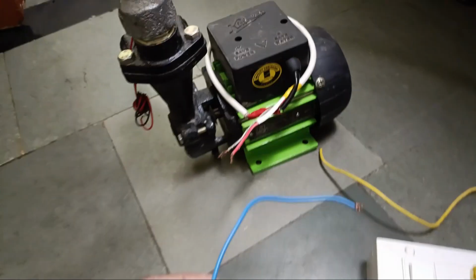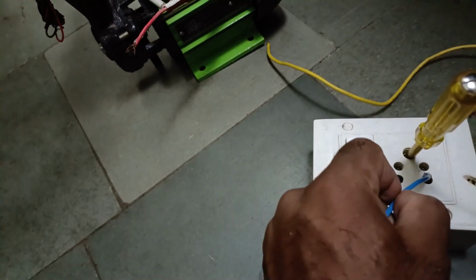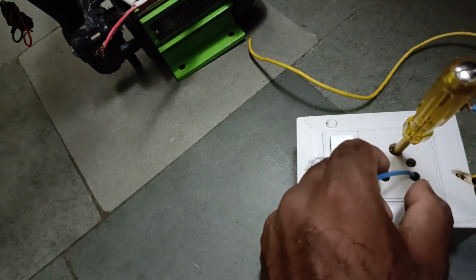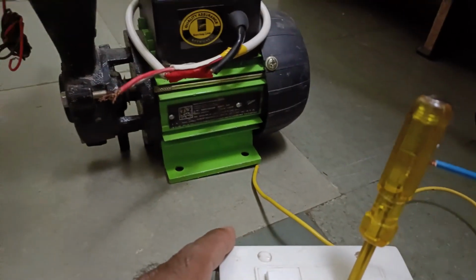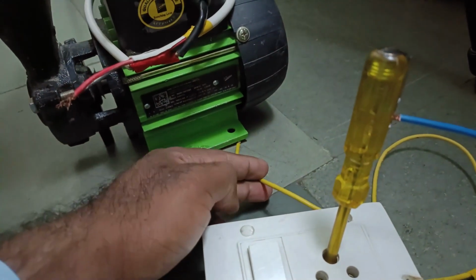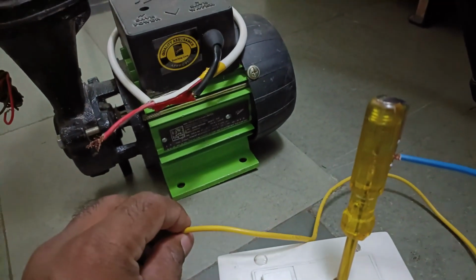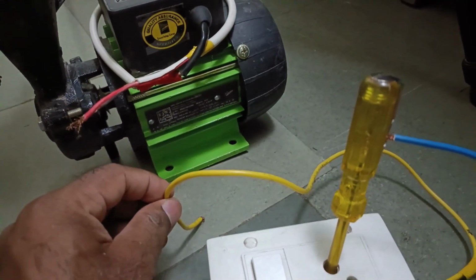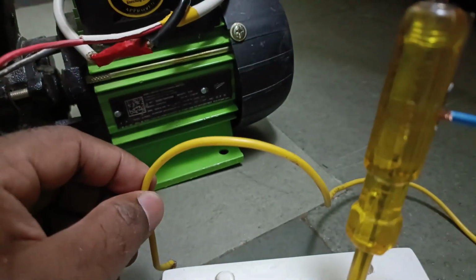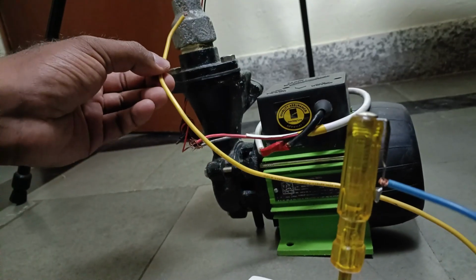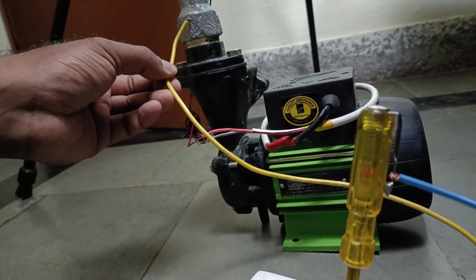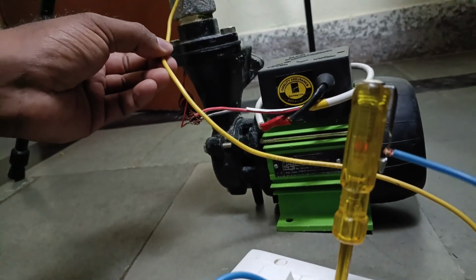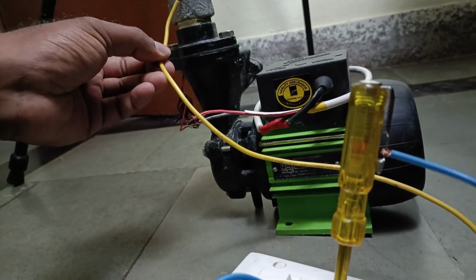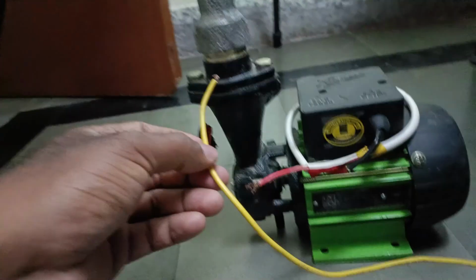After this, I take this wire and connect it to the phase supply terminal of the socket in this way. Now I will do one thing: I take this earthing wire and touch it here. Is the light glowing? The tester is slightly glowing now, you may not be able to see it in this video. So I take this wire and touch it with the motor body, and you can see that if I connect the earthing wire to the motor body, the tester is glowing here.